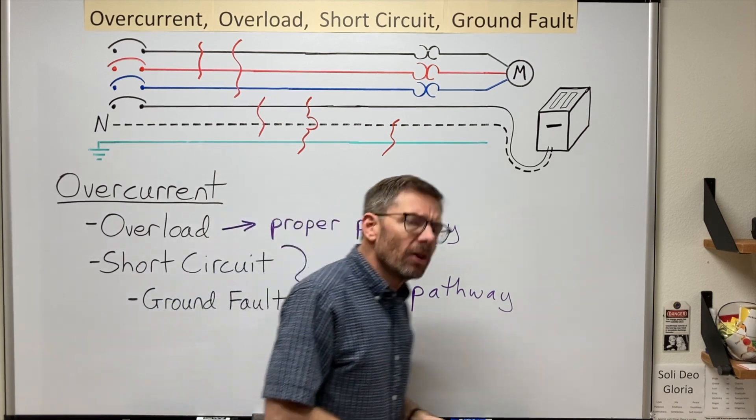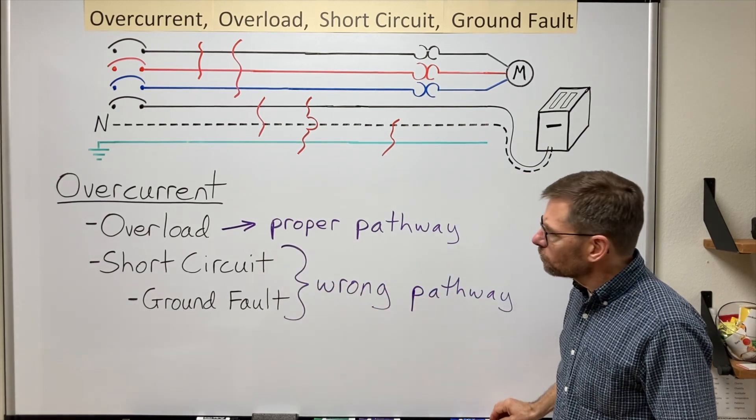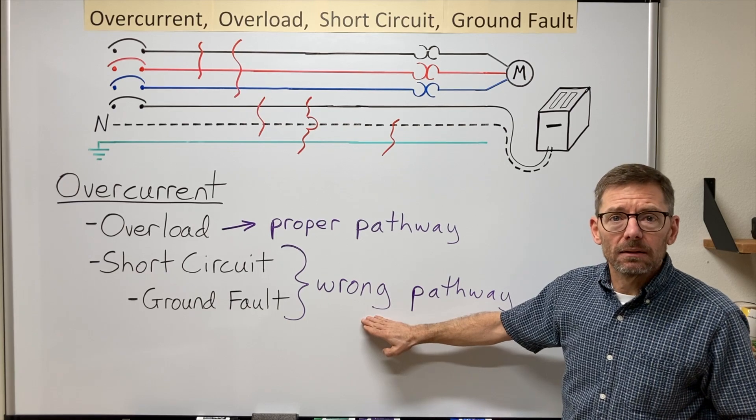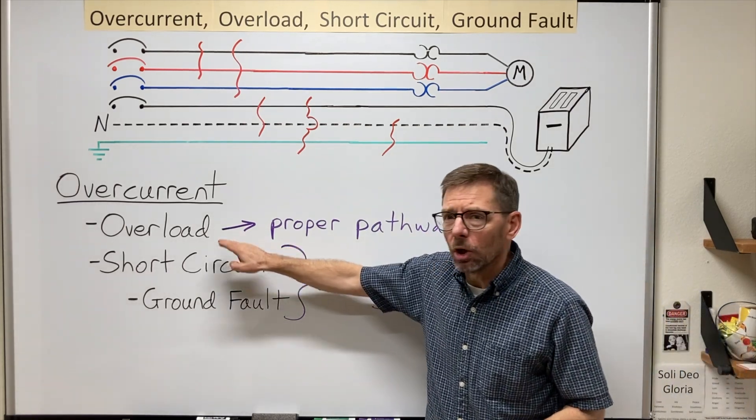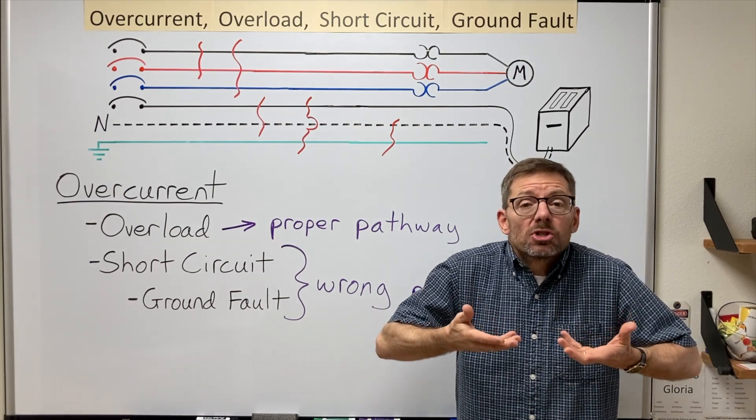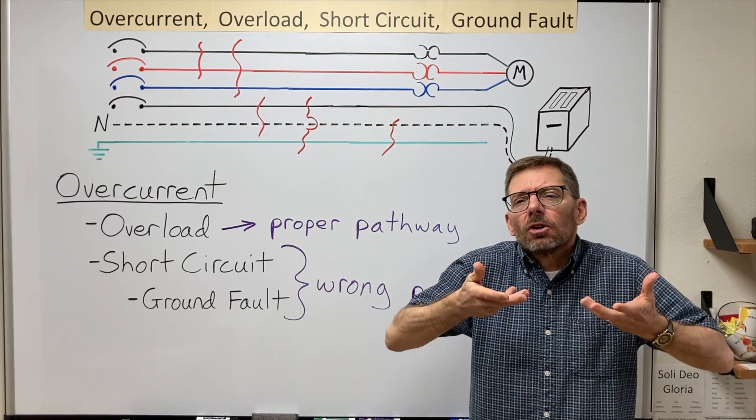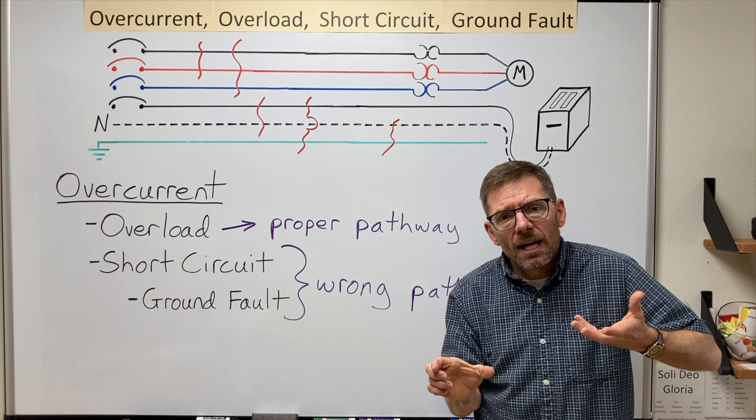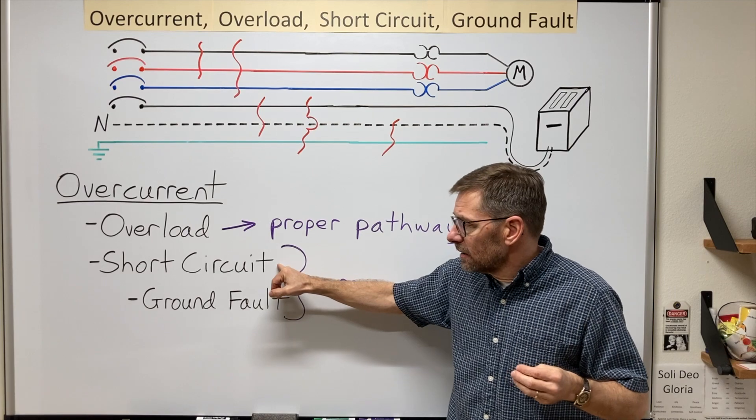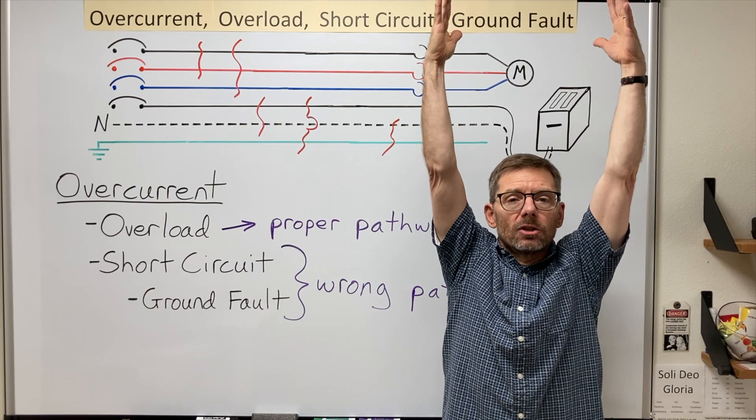So what are the main differences then between my overloads and these short circuits? I mentioned proper pathway, wrong pathway. But also, let's think that an overload often exceeds the rated current as much as four or six times, maybe more. But it exceeds the current for a period of time, or the device will open. But a short circuit often greatly exceeds the rated current.